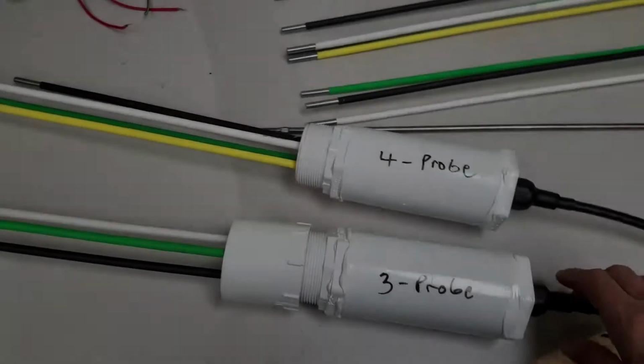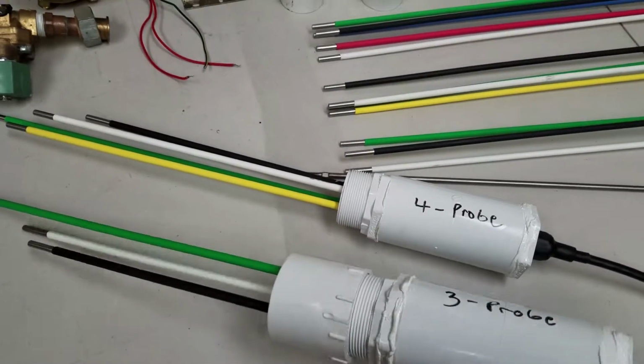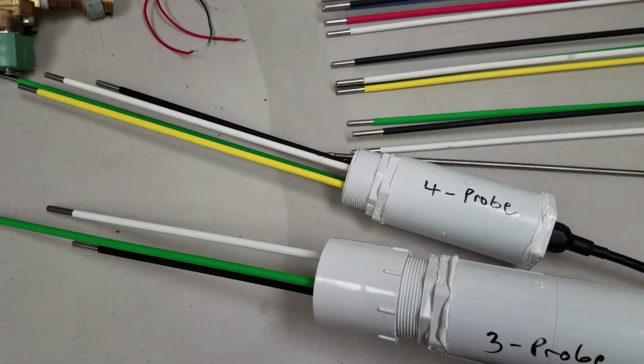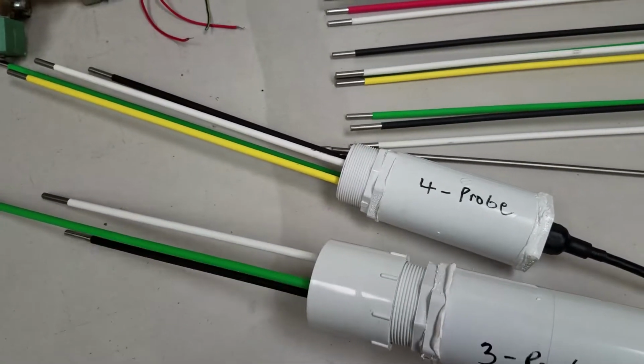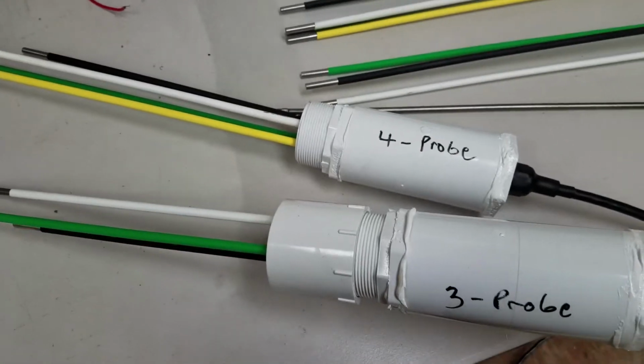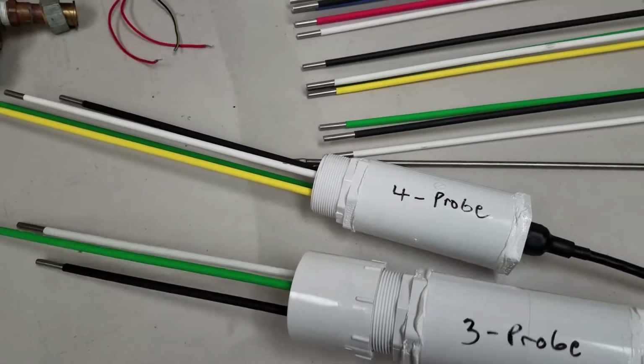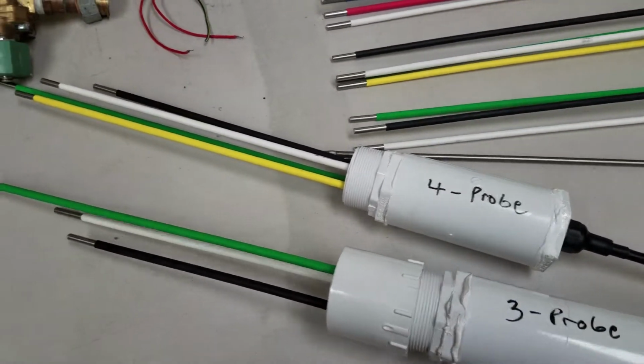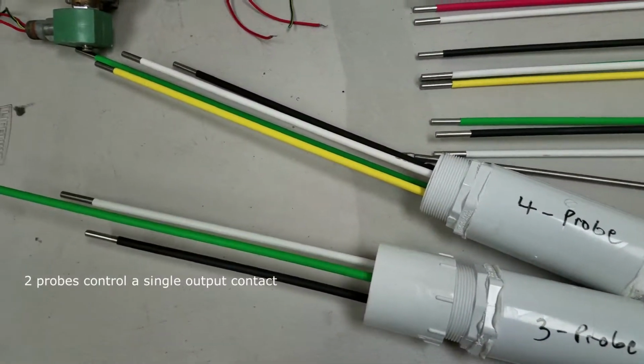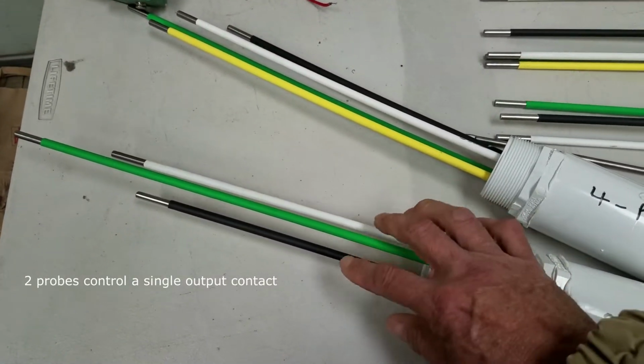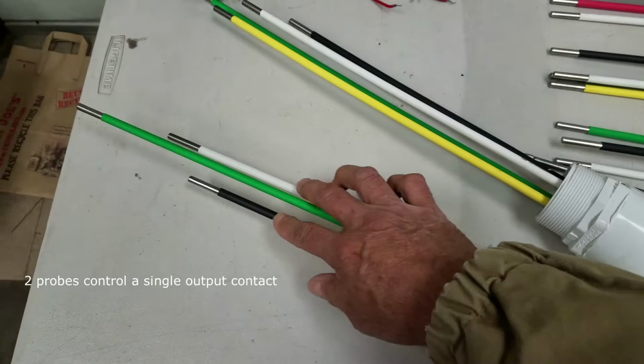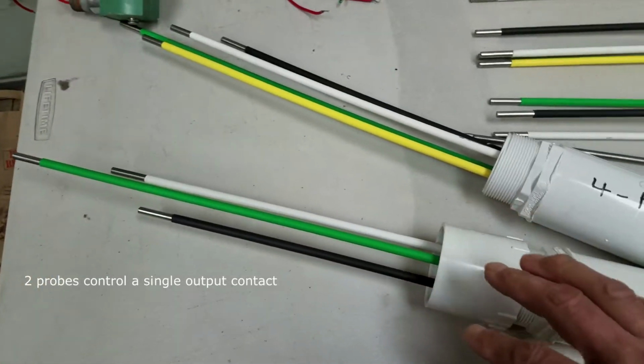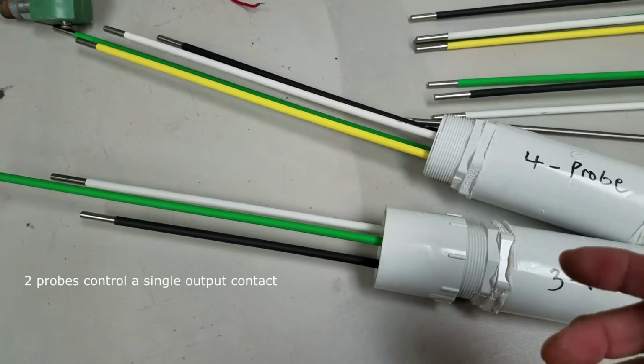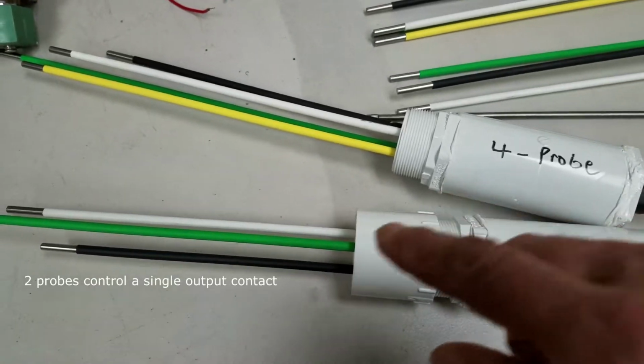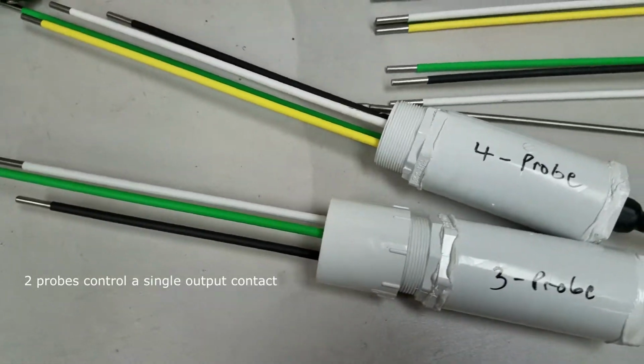The 3 probe is your basic unit, which has 3 probes. 2 of the probes control water level. I'll show you. And all the other models have this function of controlling a water level with 2 probes. Your white and your black probe, your water stays between the white and black probe, and your green probe is your reference probe.